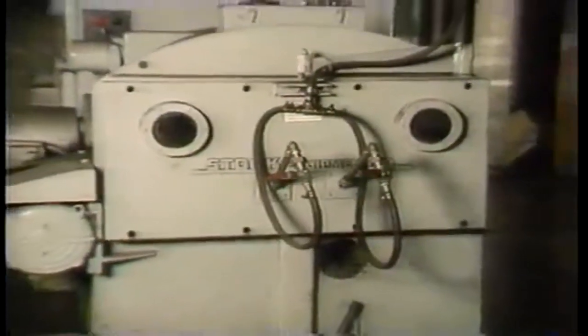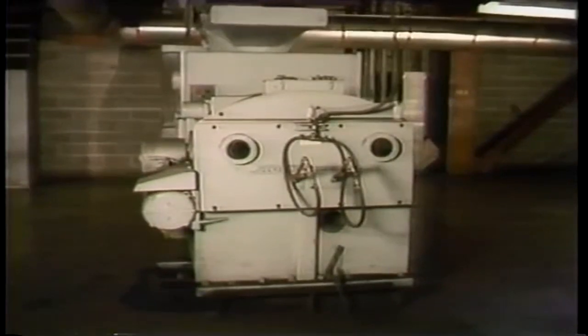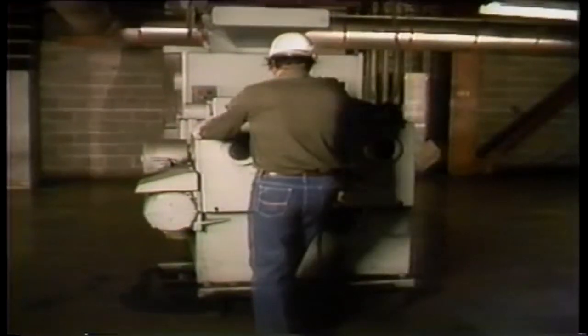For the most part, the equipment fires we've discussed are contained within the equipment and do not normally represent an immediate danger to the operation of the plant. However, like any abnormal condition, an operator must carefully monitor the situation to make sure that it doesn't get worse. Just as it is necessary to understand the proper action to take in the event of an equipment fire, it's also necessary to understand what not to do. The fires discussed occur inside closed equipment, and in many cases there are access doors on these pieces of equipment. If an equipment fire is suspected, under no circumstances should an access door be opened. By leaving access doors closed, you increase the likelihood that the fire will consume all available oxygen and eventually smother itself. Opening an access door has exactly the opposite effect — an immediate supply of oxygen is made available for combustion, which could make the fire worse or even cause an explosion.